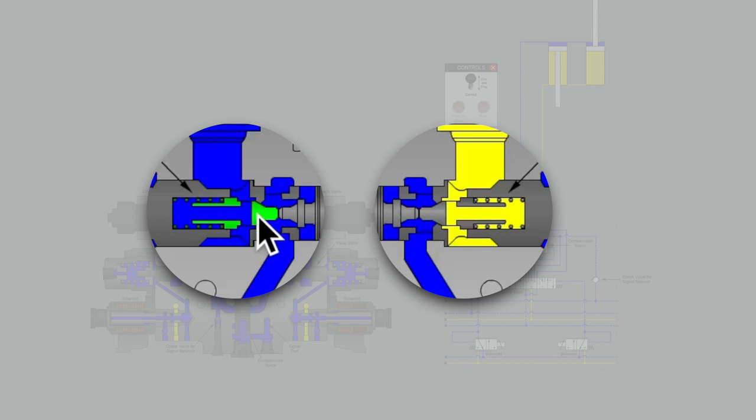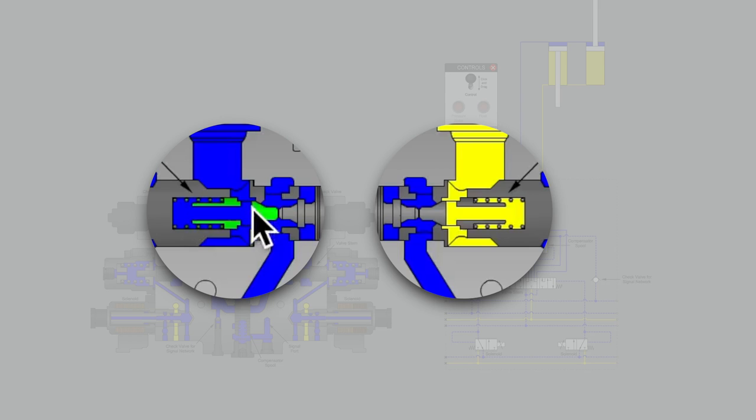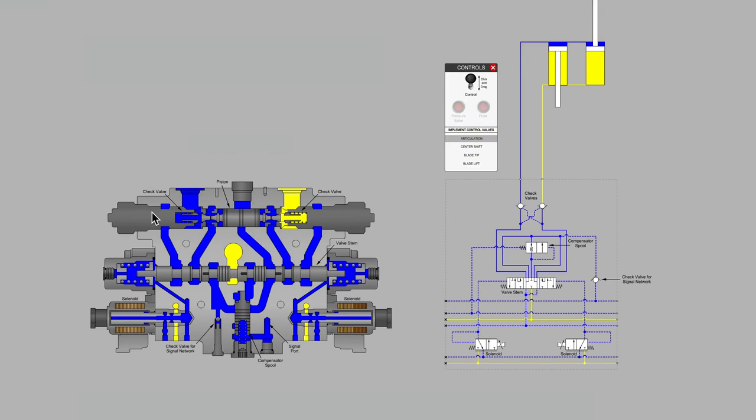But then also notice this, there are springs behind these check valves to help them close. You see the little green circles there when I light up the component, there are springs there. So if you were to unthread this cartridge and pull it out of the valve bank, oh, of course, never do that while the machine is running. Make sure that you're shut down, that all safety chocks and safety links on the machine are in place, that you have depressurized. Take all precautions, please.